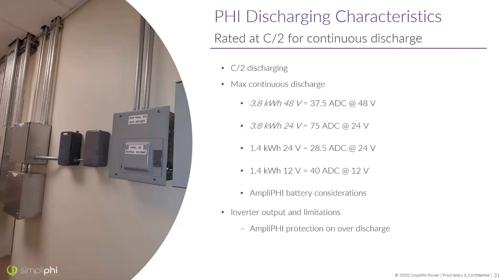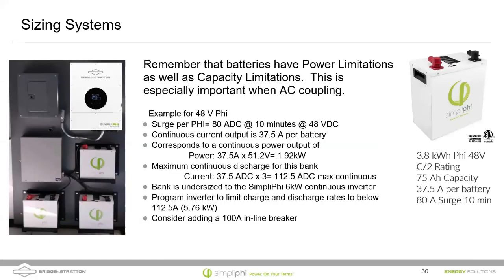Nathan, we had one question. If you could go back one slide. The picture on the left there, we see some wires coming from the batteries going into that Midnight Solar combiner box. Do those wires need to be the same length, or can the battery management system remedy that? Yeah, that's a great question. The cables running from each battery to the combiner box need to be the same length. The reason is that when a large amount of current is being drawn through cables, there's a voltage drop. The load drops the voltage at the combiner below the battery voltage so that the batteries start discharging into the combiner. If one battery has a longer cable than the others, there's more resistance in that longer cable, so it will output less current and do less of the work. So that we equally load each of those 3 batteries, we want those cables all to be equal length when they're in parallel.